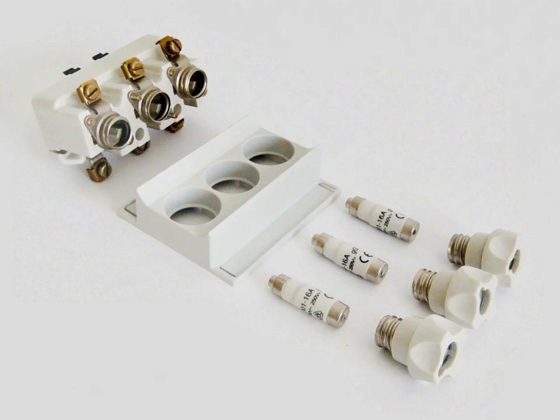Under mechanical stress, it is possible for the cover to crack partially or fully, uncovering the conducting element. It may happen if a fuse holder was accidentally dropped or someone was using too much force to screw it in. Uncovered metal envelopes present a serious risk of shock and should be replaced immediately under extreme precautions by trained personnel. The smaller end cap, the top of the bottle, has a diameter that varies with the fuse rating. Higher ratings have wider end caps.